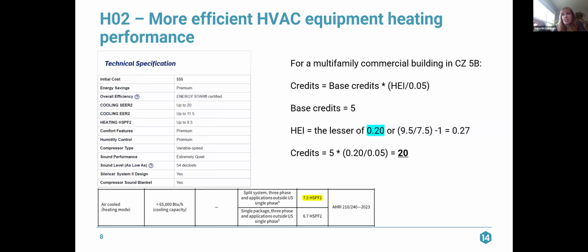So we're going to calculate our HEI, which is going to be the lesser of 0.20 or 9.5 divided by 7.5. So my 9.5 HSPF2 divided by that 7.5 HSPF2 I have highlighted down there, minus 1. So that gives me a 0.27. 0.20 is less than that. So then we're going to have 5 times 0.20 divided by 0.05, which gives me 20 credits. So a fair number of credits available there.